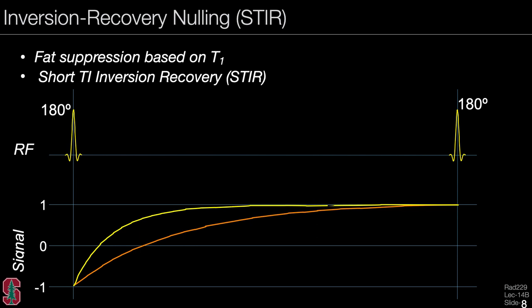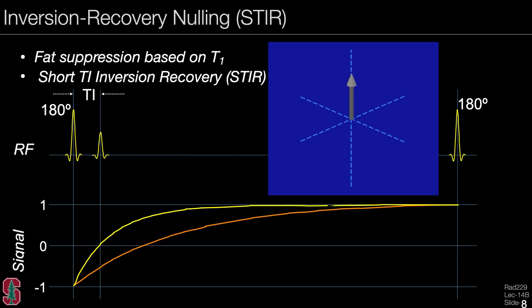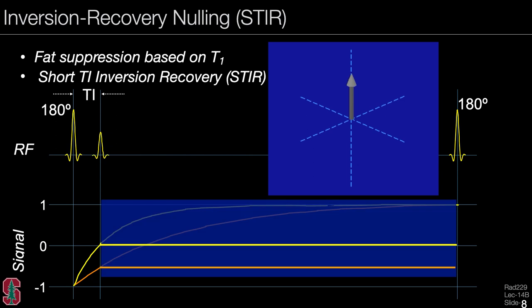Another very common approach to magnetization preparation is inversion recovery, often used for nulling, such as in the STIR approach—short TI inversion recovery, sometimes called short tau inversion recovery. We start the sequence with a 180-degree inversion, and the signals recover with different T1 values. We then excite at the null point for whatever tissue we want to null—in this case, fat. So we excite when that trace passes through zero, giving us a short inversion time. Ideally, the fat signal has been nulled. This is another form of fat suppression based on the T1 difference between fat and other tissues, though we also lose some SNR from other tissues.